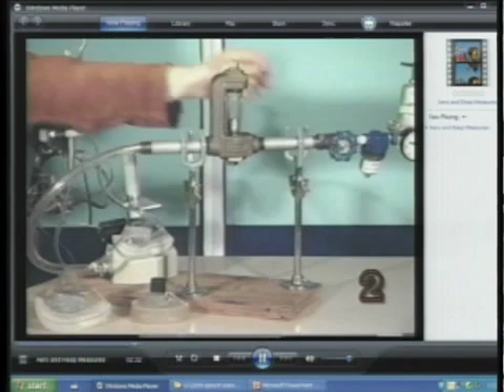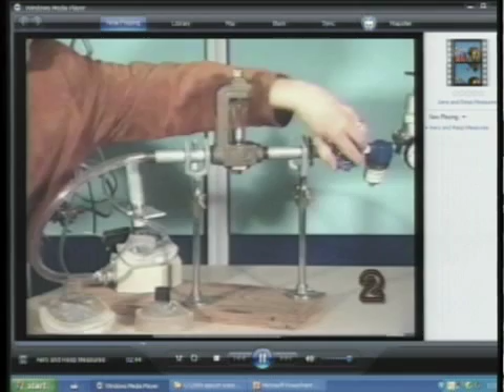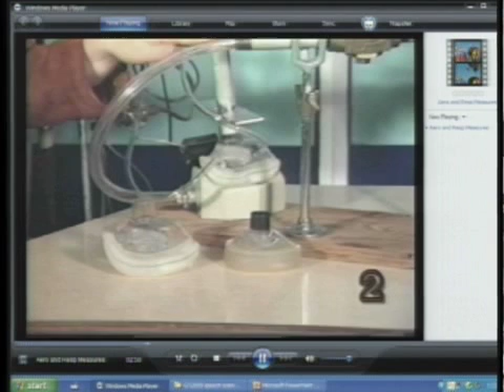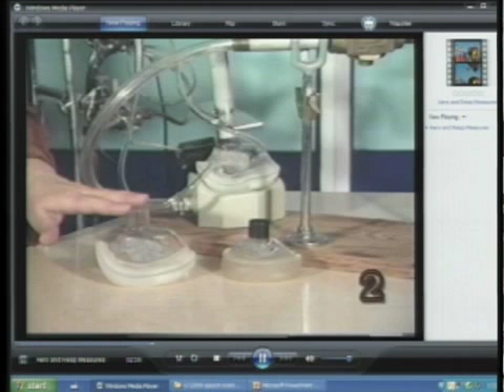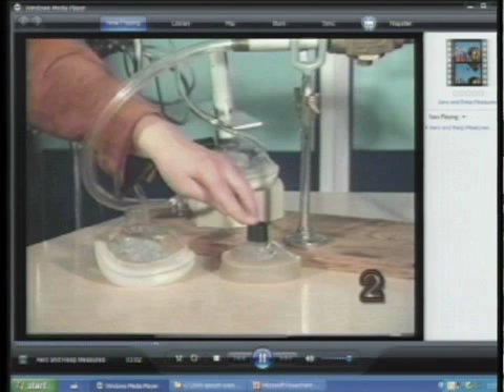Now I'm going to demonstrate how we calibrate for airflow, air pressure, and air volume. To calibrate for the airflow, we place the pneumotachograph on the mold. While using a device called a rotometer to indicate the flow moving through the mask transducer system, we record this signal and use it for later reference. We calibrate for airflow for each mask size that we use. So this is the medium-sized mask, and this is the one that's used for adult females and teenagers. We use the large-size mask for adult males, and this is the small-size mask that's used for the younger children.